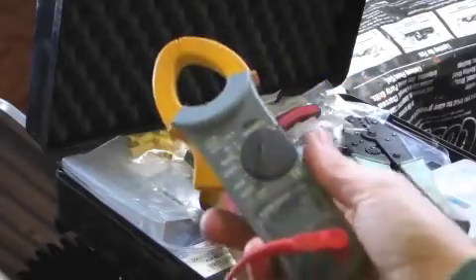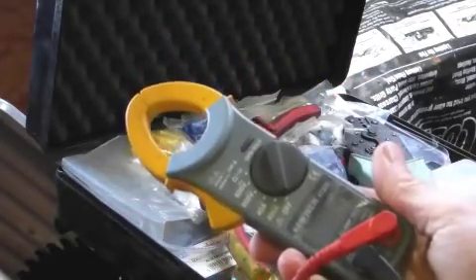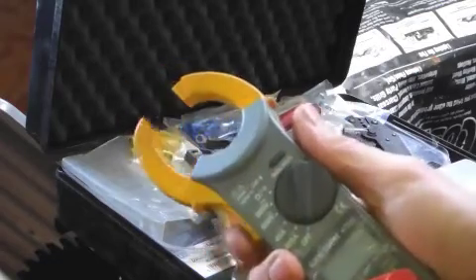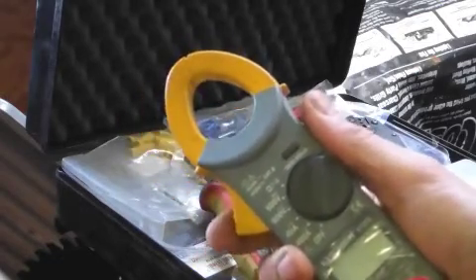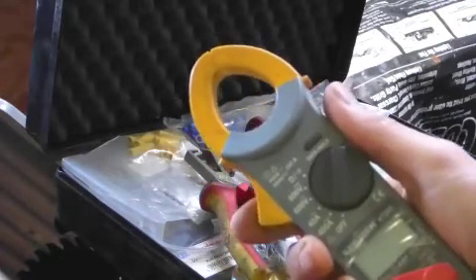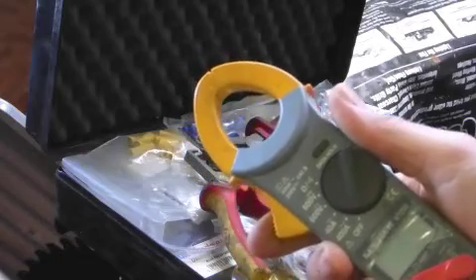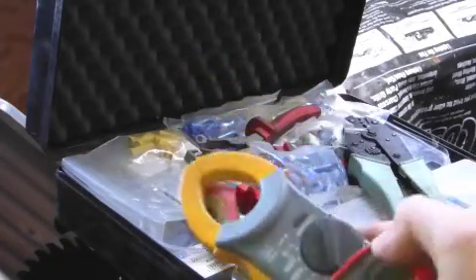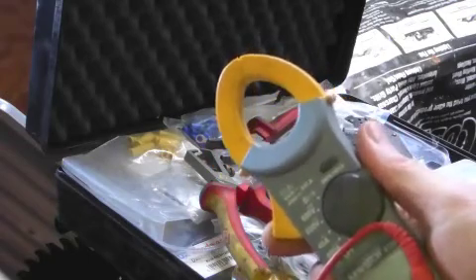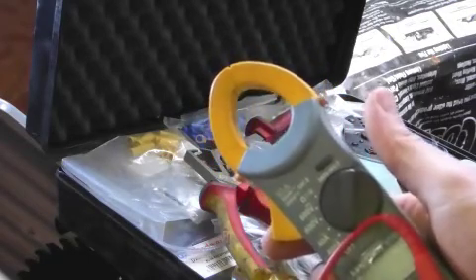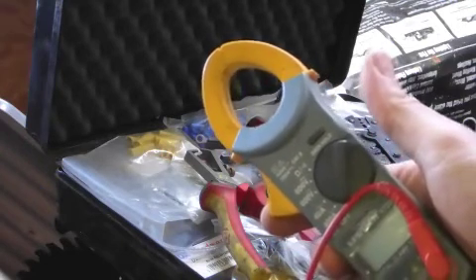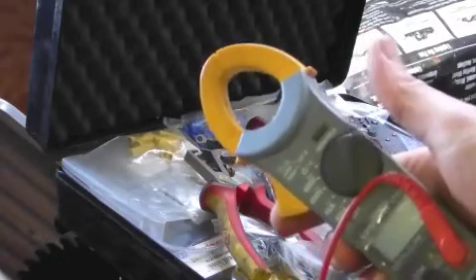Another bit of kit which is pretty much essential for the balancing job of balancing the converter is a clamp meter. This allows you to measure currents simply by clipping the meter around the cable without having to introduce a meter into the circuit. Introducing ammeters into three-phase circuits is particularly difficult because of the high starting current. Most multimeters will handle a current of around 10 amps, which is fine for the running current of the motor, but the starting current is far in excess of that.